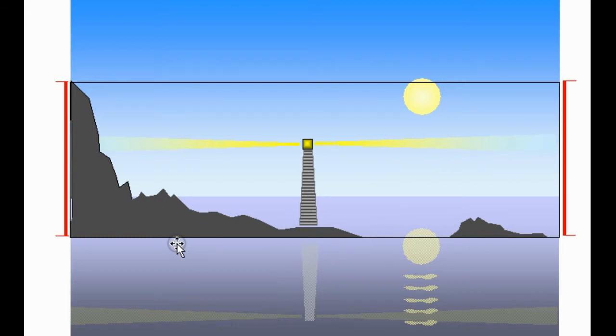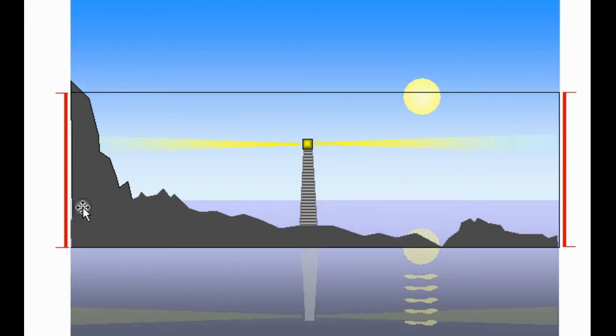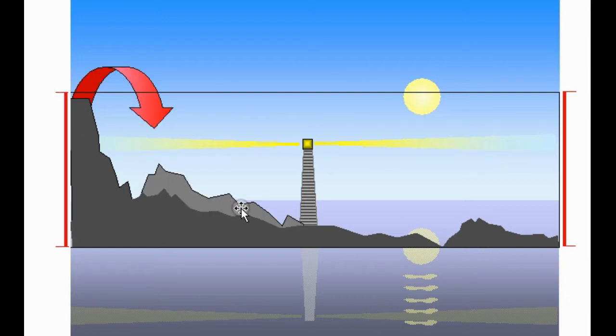Going back to the ocean view, we can continue to reduce the attenuation, making our analyzer more sensitive, but here we run into a problem, because now this high energy signal at the left-hand side has exceeded the dynamic range of the analyzer. The analyzer cannot plot this information, so it gets distributed to other parts of the spectrum, producing a false result.